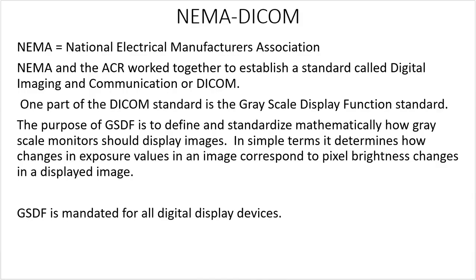NEMA — the National Electrical Manufacturers Association — and the ACR worked together to establish a standard called Digital Imaging and Communications, or DICOM. One part of the DICOM standard is the Grayscale Display Function standard, GSDF. The purpose of GSDF is to define and standardize mathematically how grayscale monitors should display images. In simple terms, it determines how changes in exposure values in an image correspond to pixel brightness changes in a displayed image. GSDF is mandated for all digital display devices.